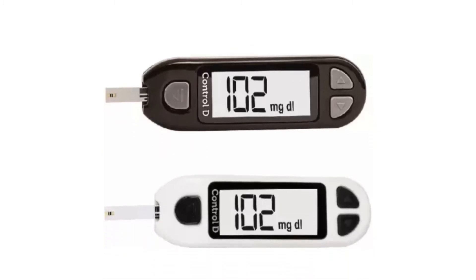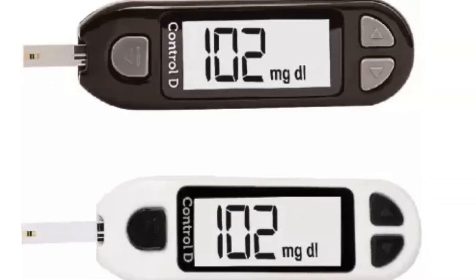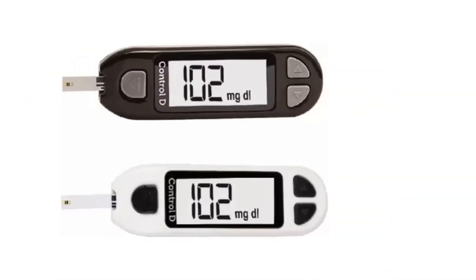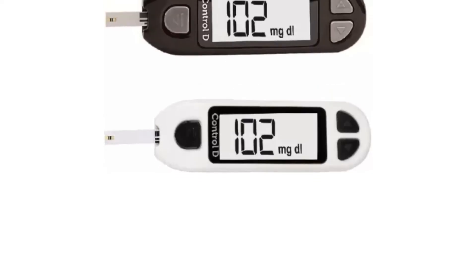It saves the last 500 results for future reference and better tracking. It is powered by a battery and features an LCD display. It also has an ejection button for easy operation and minimal contact, thereby preventing contamination. The machine requires a minimum of 0.5 microliters of blood, can measure sugar levels in the range of 20–600 mg/dL, and gives results in 5 seconds. The glucometer comes with a lancing device, 10 lancets, and 10 strips so you can start using it as soon as it is delivered.